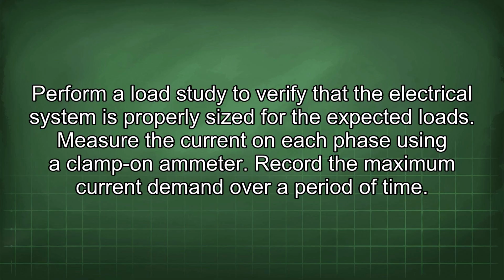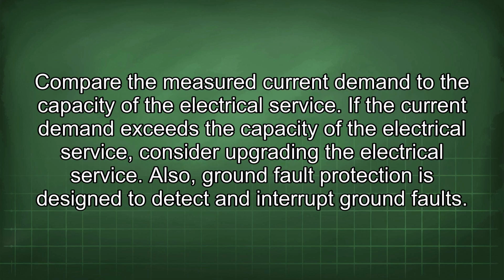Measure the current on each phase using a clamp-on ammeter. Record the maximum current demand over a period of time. Compare the measured current demand to the capacity of the electrical service. If the current demand exceeds the capacity of the electrical service, consider upgrading the electrical service.